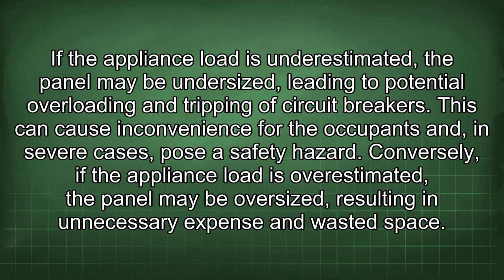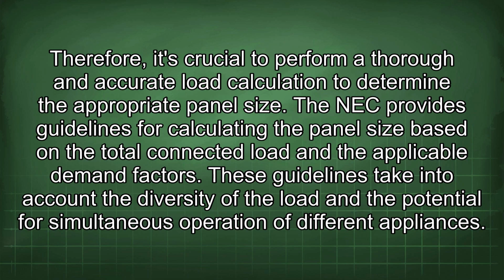Conversely, if the appliance load is overestimated, the panel may be oversized, resulting in unnecessary expense and wasted space. Therefore, it's crucial to perform a thorough and accurate load calculation to determine the appropriate panel size. The NEC provides guidelines for calculating the panel size based on the total connected load and the applicable demand factors. These guidelines take into account the diversity of the load and the potential for simultaneous operation of different appliances.